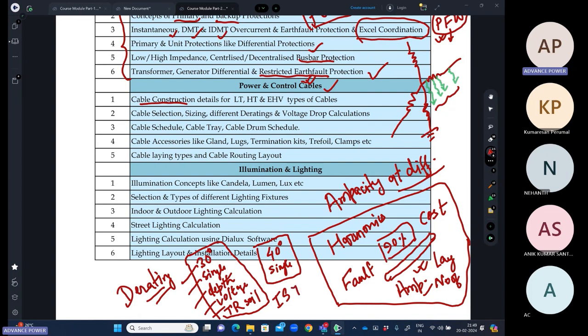The manufacturer will give you the cable based on the IS which is applicable. Suppose I am saying 7098, they will design the cable based on this. Now it's your choice what insulation and what material of the cable you want to purchase, depending upon the ampacity and the temperature rise requirements. We'll discuss those things: selection, sizing, the ratings, voltage drop calculations. We'll do it for AC single phase, for three phase, and for DC cable voltage drop calculations.